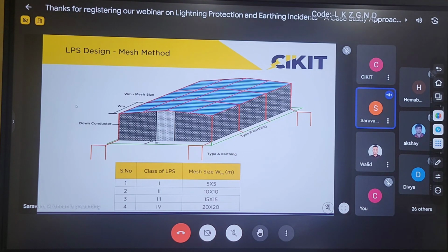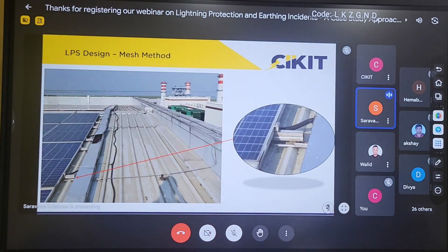So this is the problem with the mesh method. Nowadays many people are not going for the mesh method because of rooftop solar installations. If we are installing solar on the rooftop, then the height of the panels will be higher than the mesh conductor, and the panels will be placed over this mesh conductor. So the structures won't be protected by this mesh conductor. So if I want to protect this building after installing solar, then I have to modify the design by installing vertical air terminals using either the protection angle method or the rolling sphere method.